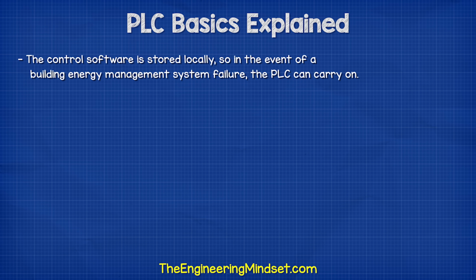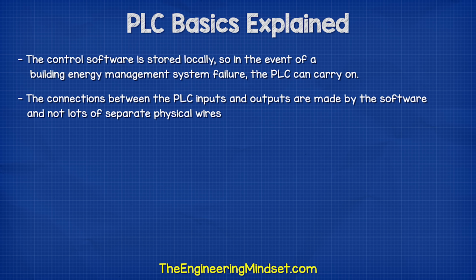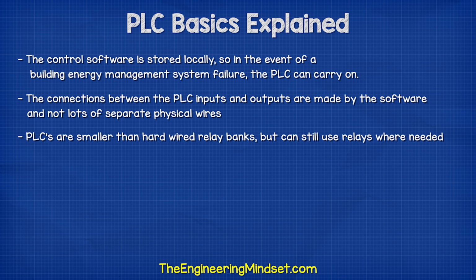There are many advantages of PLCs, but some of the main ones are as follows. The control software is stored locally, so in the event of a building energy management system failure, the PLC can carry on working. The connections between the PLC inputs and outputs are made by the software, and not by lots of physical wires. PLC installations are smaller than hardwired relay banks, but they can still use relays where needed.